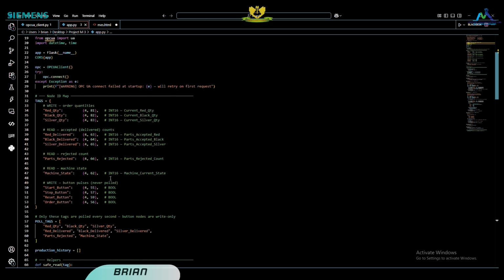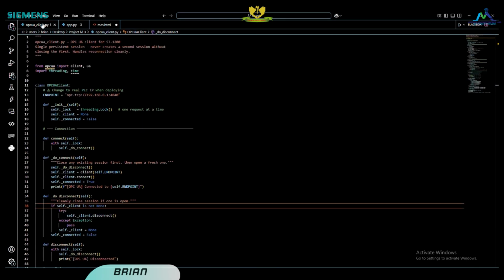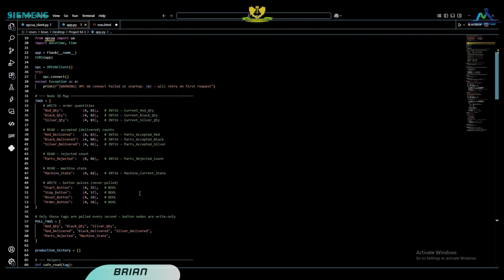The client is wrapped in a reconnection layer, so if the connection drops, it automatically tries to re-establish the connection before trying to read or write. So all nodes, namespaces, IDs, and endpoint addresses are centralized in a single configuration, making it straightforward to adapt to any OPC-UA-enabled controller. So the interface is hosted as a local web application, and all live data flows directly from the PLC through this OPC-UA connection.